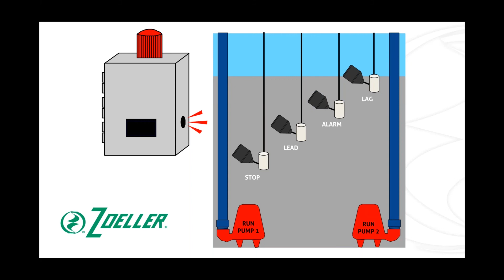They have no pumps. So like I said, this is a float arrangement that I just want you to think about. I want you to understand. I want you to get the idea of why I've opted to do that. It might not be right for every situation out there. I've just clicked on to the next slide here. You can see in this slide, the lag float has now come up, and that's when it calls for pump 2 to come on. And so now both pumps are working together. Again, this float arrangement, like I said, might not be right for every system out there, but I just want you to get that idea and understand this. To me, this is what's going to make you the professional. It's going to make you the expert out in the field. It's going to allow you to make the best decision for your customer.